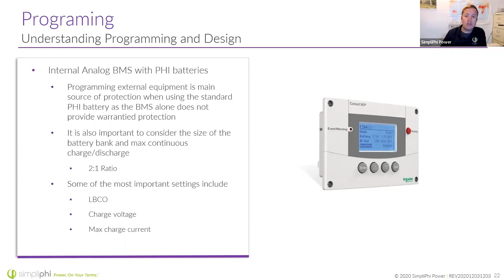To reiterate, the digital ones can auto-populate set points. The SimpliPhi batteries automatically detect how many batteries are in the system, because we have little comm cables going between them, and this yellow one is the home run to the piece of equipment. These are our bus bars here. It can transmit that data and auto-populate the set points based on its battery bank size.